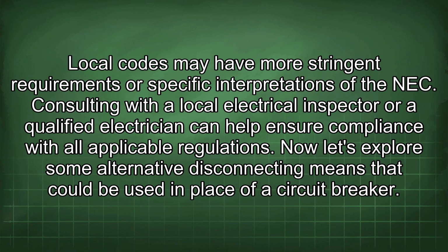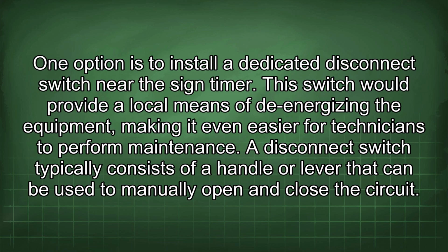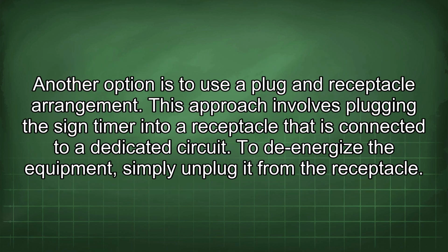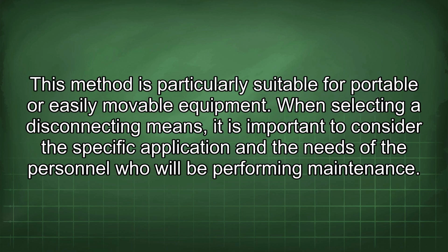Now let's explore some alternative disconnecting means that could be used in place of a circuit breaker. One option is to install a dedicated disconnect switch near the sign timer. This switch would provide a local means of de-energizing the equipment, making it even easier for technicians to perform maintenance. A disconnect switch typically consists of a handle or lever that can be used to manually open and close the circuit. Another option is to use a plug and receptacle arrangement. This approach involves plugging the sign timer into a receptacle that is connected to a dedicated circuit. To de-energize the equipment, simply unplug it from the receptacle. This method is particularly suitable for portable or easily movable equipment.